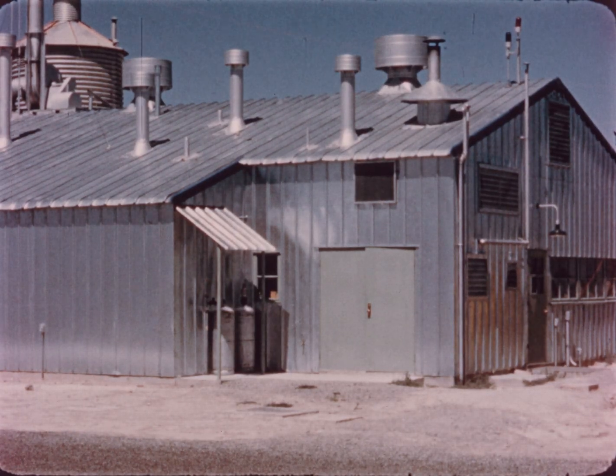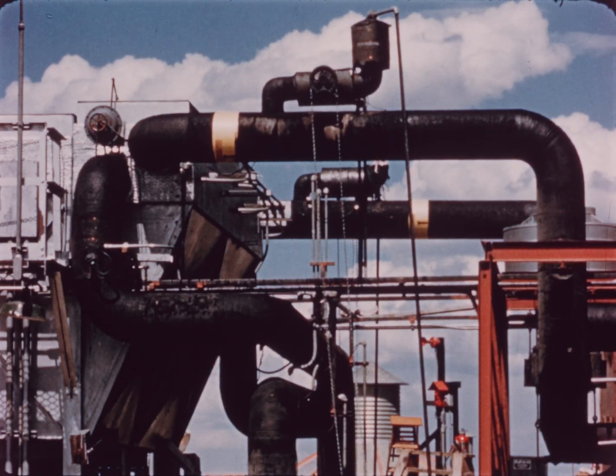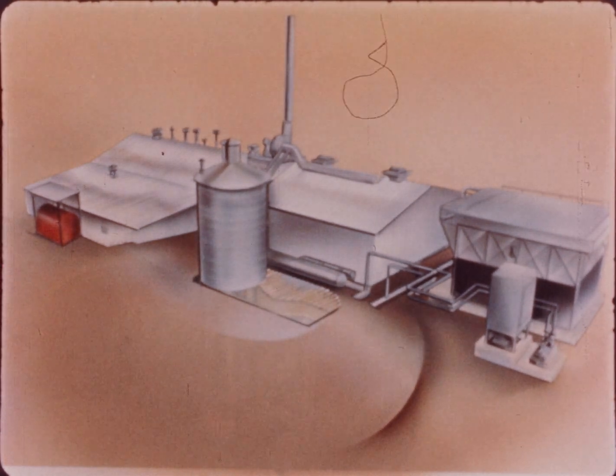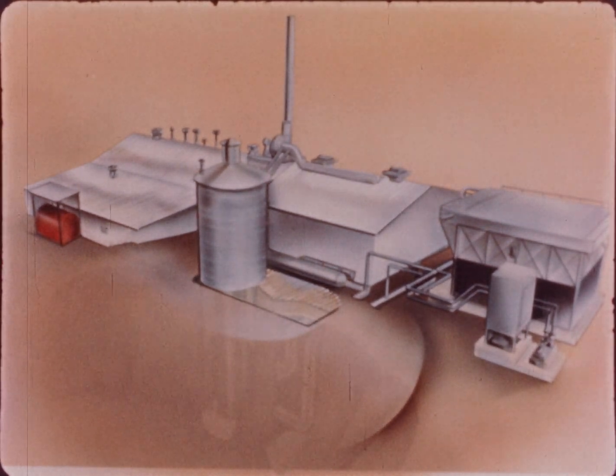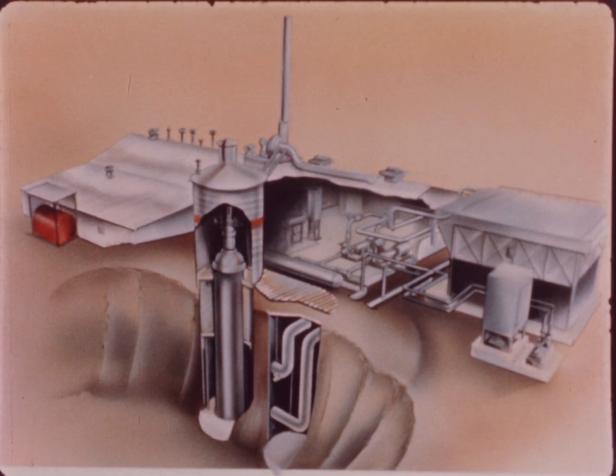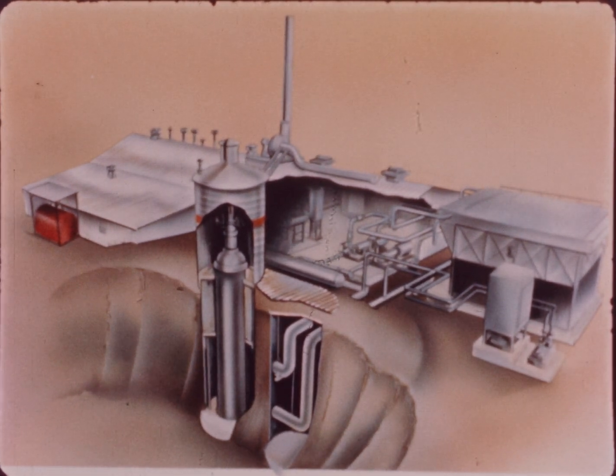As a result, a compound from the polyphenyl group was selected as the hydrocarbon for OMBRE. The OMBRE cooling system contains over 19,000 liters of a polyphenyl mixture whose characteristics, once melted, are similar to those of water.